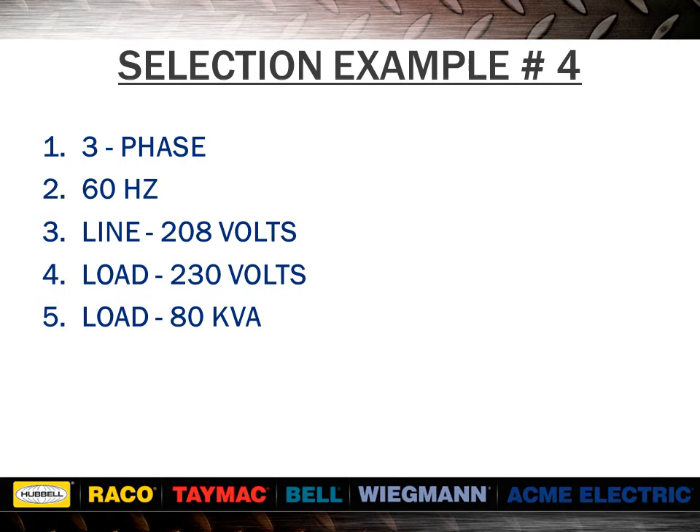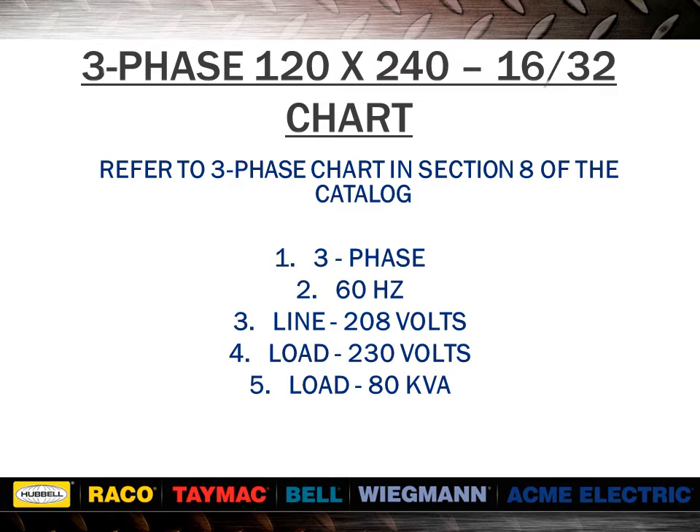In example 4, we use a three-phase application. We would take 208 volts and subtract from 230 volts, giving us 22 volts. As in our previous examples, we would find the desired voltage combination across the top of the chart in the boosting section of the catalog. Reading down the chart, we would find a kVA value of 80 kVA or greater. In this case, we find 82.99 kVA. Reading to the far left of the chart, we find item number T111687. Looking at the bottom of the voltage column, we find the quantity required and the wiring diagram to use.